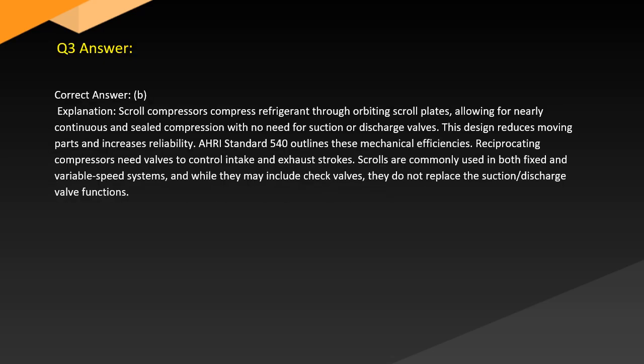Answer. Correct answer: B. Explanation. Scroll compressors compress refrigerant through orbiting scroll plates, allowing for nearly continuous and sealed compression with no need for suction or discharge valves. This design reduces moving parts and increases reliability. AHRI Standard 540 outlines these mechanical efficiencies. Reciprocating compressors need valves to control intake and exhaust strokes. Scrolls are commonly used in both fixed and variable speed systems, and while they may include check valves, they do not replace the suction and discharge valve functions.